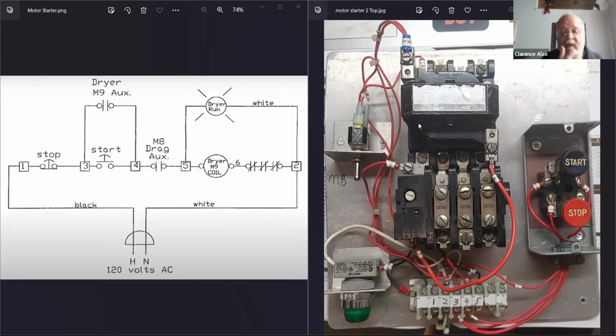Now you've got that pressure going to one side of the coil. That's good because we know we have to have high pressure on one side. And on the other side of the coil, what are we expecting, Isaac? Low pressure, absolutely. If you get anything else but that, you can't expect that coil to pull in. So if it says 120 volts on one side and 120 volts on the other side, don't go changing out the coil - you've got to make sure it's got its proper input. Same thing with the light: 120 volts on one side, 0 on the other.